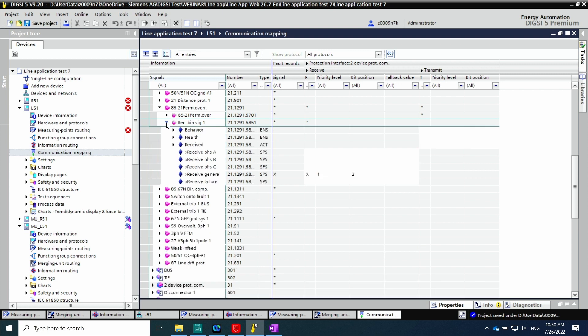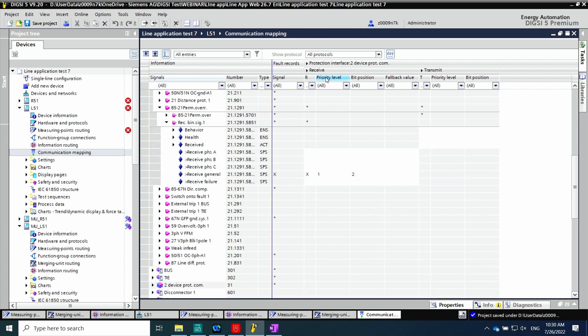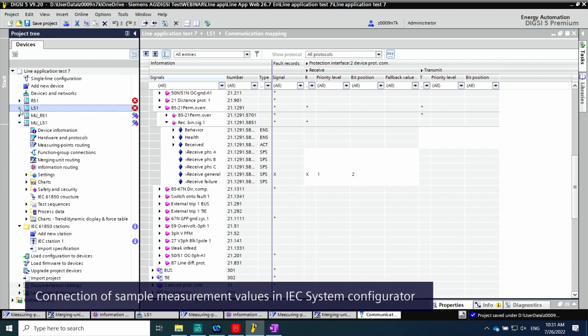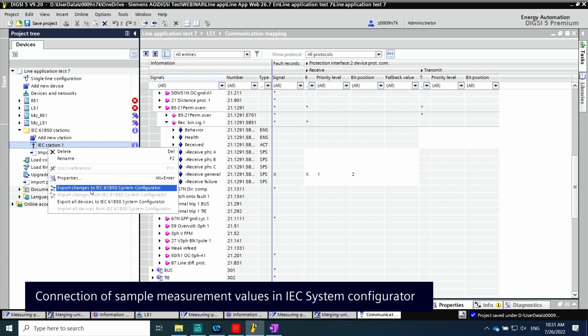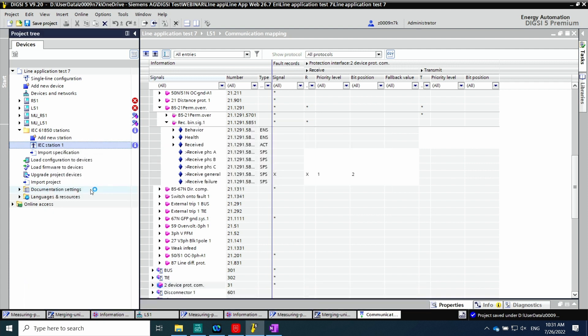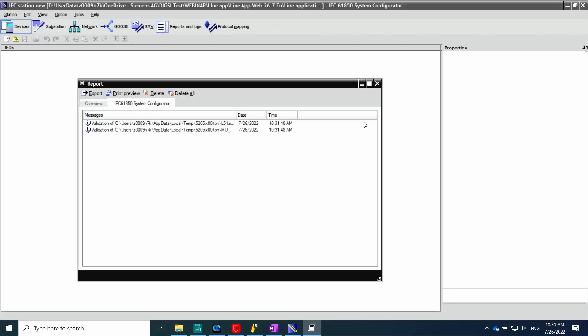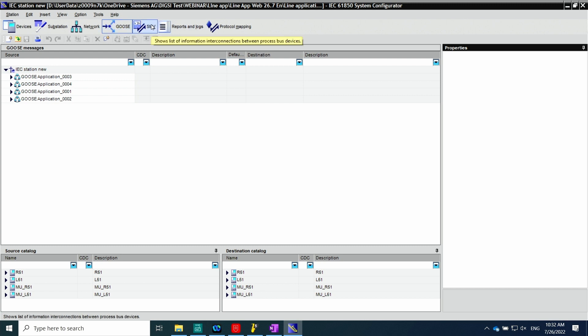The final step is to connect the sample values in the IEC 61850 station. SCL export is required to export the changes to the IEC 61850 system configurator. With the system configurator, all communication links regarding IEC 61850 communication are done. Here there are different tabs — one tab for GOOSE and one tab for sampled measured values.